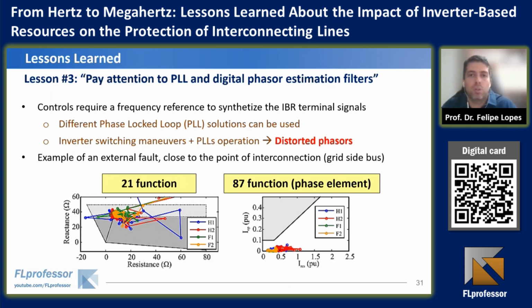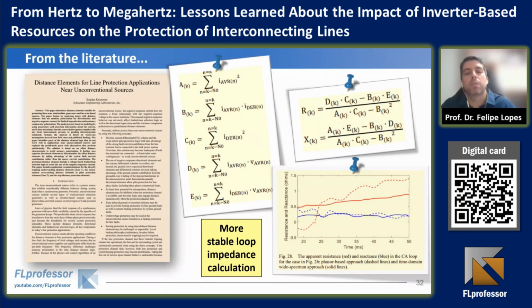And these problems of distorted phasors were also addressed by Bogdan in the same paper that I mentioned some slides ago, when he says that one can calculate the operating impedance directly from the time domain, avoiding the phasor estimation. And indeed, it makes sense for us, because we could notice that by avoiding the problem of the filters used to obtain the phasors, the behavior is more stable. So it's important. The literature is already addressing such an aspect.